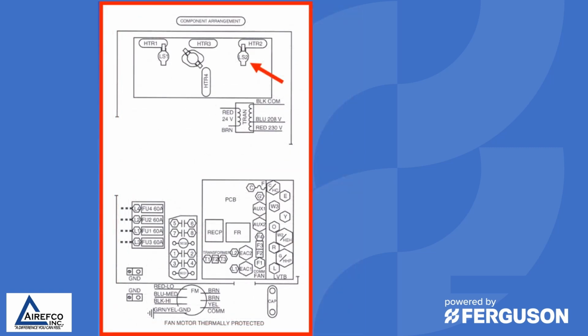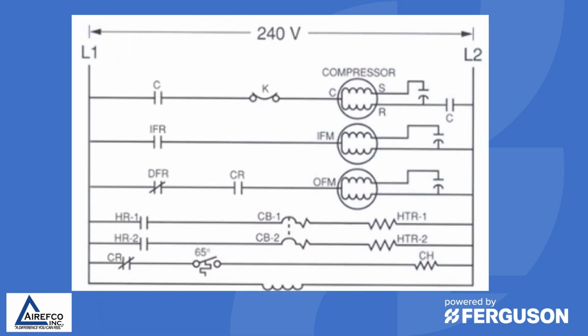The second type of wiring diagram is a component arrangement, which usually shows the physical position of the items in the control cabinet or in the unit itself. So here you'll find the various switches, transformers, control boards, fuses, heat strips, all the things that make up the unit will be depicted physically on the component arrangement diagram. There are volumes of symbols that are used on wiring diagrams. So in order to read a wiring diagram, you need to be able to interpret the symbols that they're using for various devices on the system.